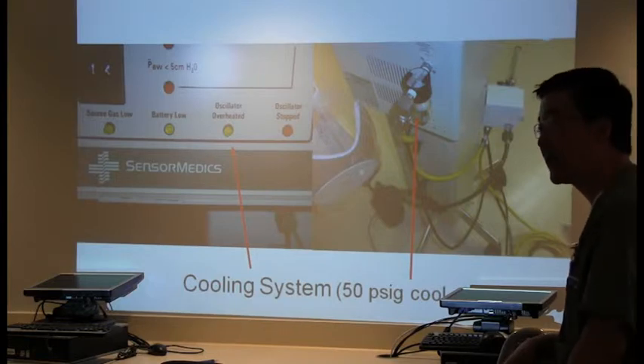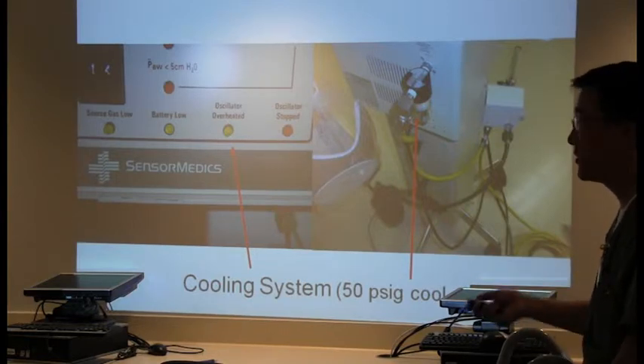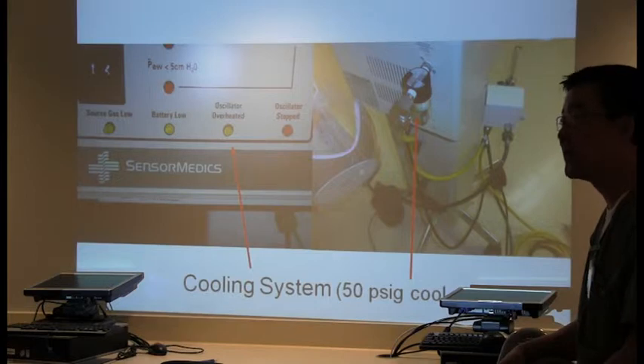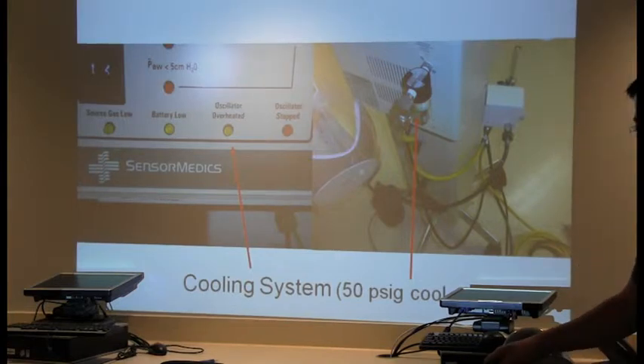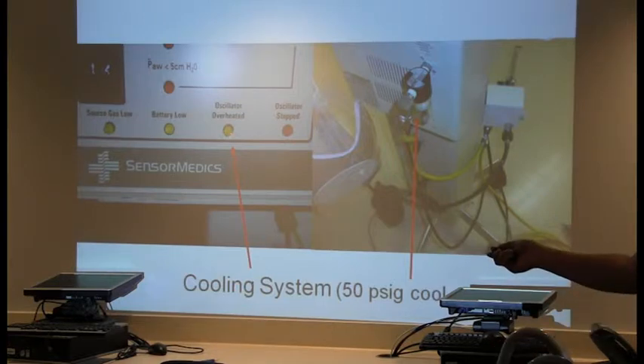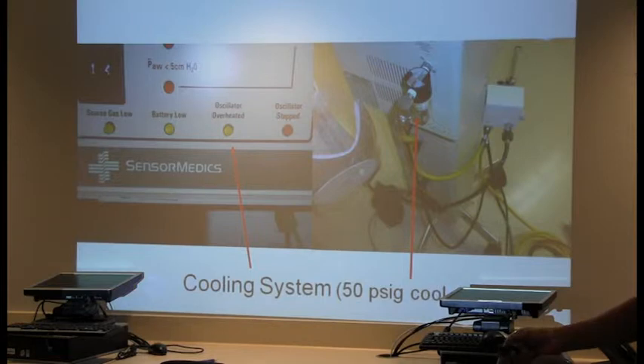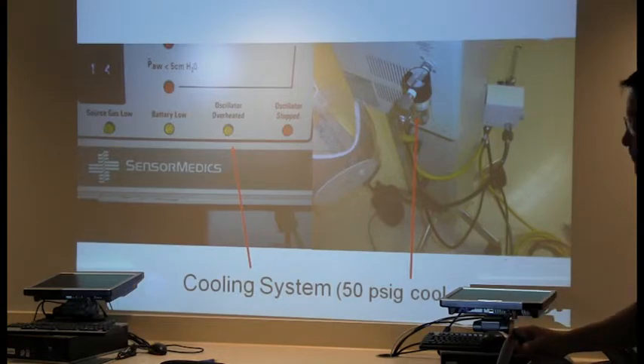And if you don't stop the ventilator and change it out, what's going to happen? You'll smell overheating, and if you continue, it'll burn and blow up. So be careful about that. If you smell something burning from the oscillator, please make sure that you don't ignore this. Take it out of the system. Anything from the wall is super cold, because that's where the system is generated.